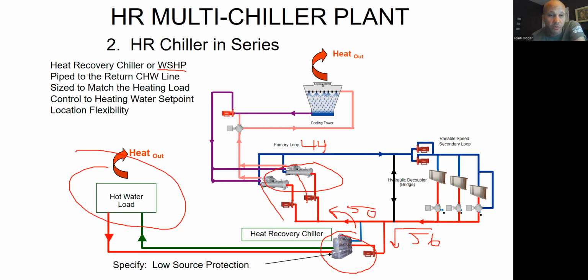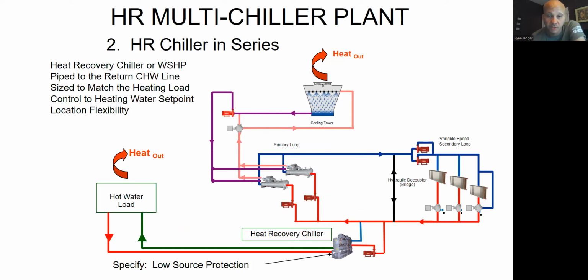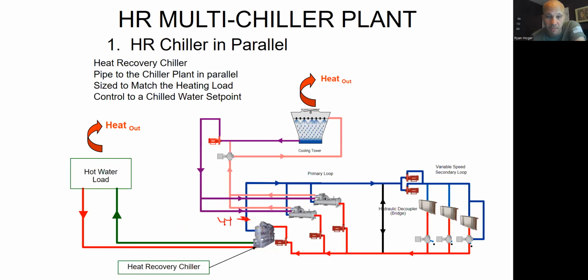So it's piped onto the chilled water line, like I just mentioned. It's once again sized for this heating load. Just run them all the time for whatever the baseline heating load is. But in this case, now I can control it to a hot water set point instead of a chilled water set point. What does that do for me? So instead of controlling it to maintain 44-degree water like this guy maintained, because that 44-degree water had to go out to the loop, and I can't start sending these air handlers warmer water. They need their 44. That's what they're sized for.